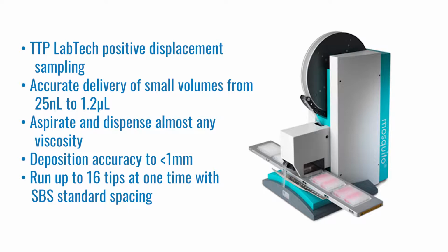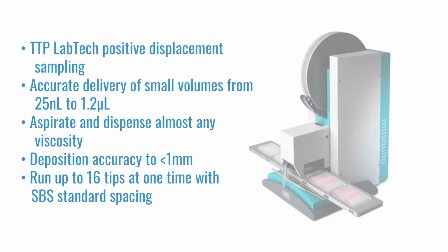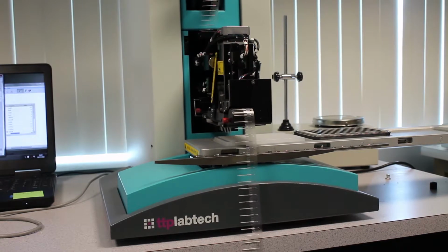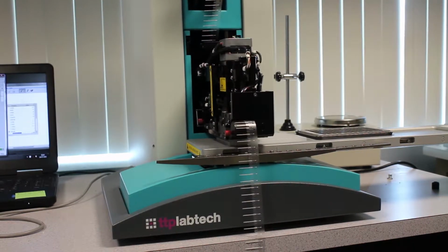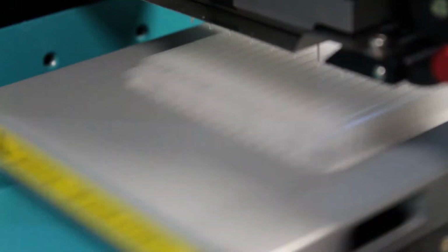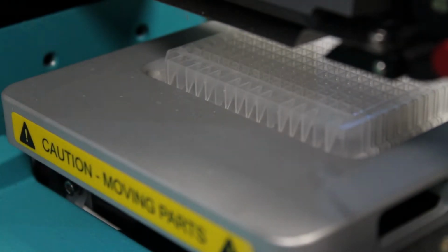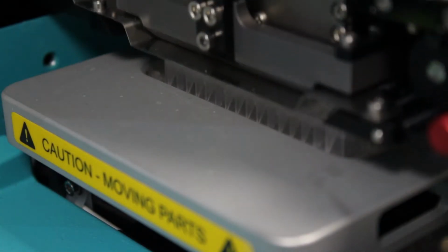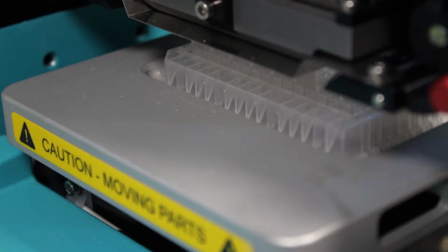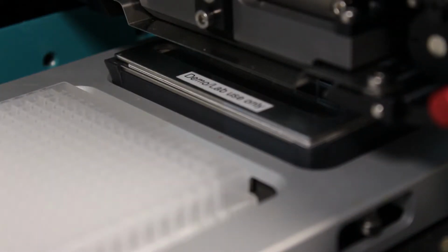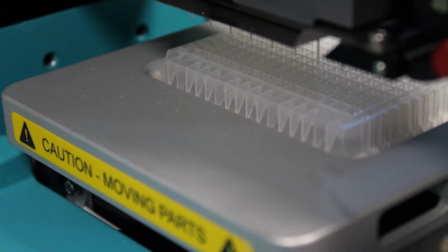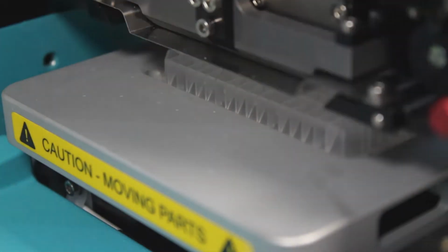The Mosquito is programmed to collect a specific volume of sample from each well of the SBS plate, move the QuickStrip into position under the micropipette tips, and eject the sample onto the QuickStrip. By design, the Mosquito performs accurate deposition of sample onto the QuickStrip consumable, which is positioned adjacent to the sample plate on the Mosquito deck. A new pipette tip is used for each sample deposition. In this case, we are eluting 1 microliter of sample onto each column of the consumable.